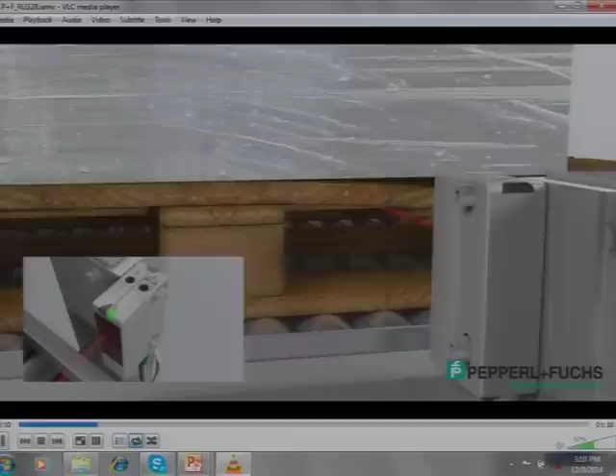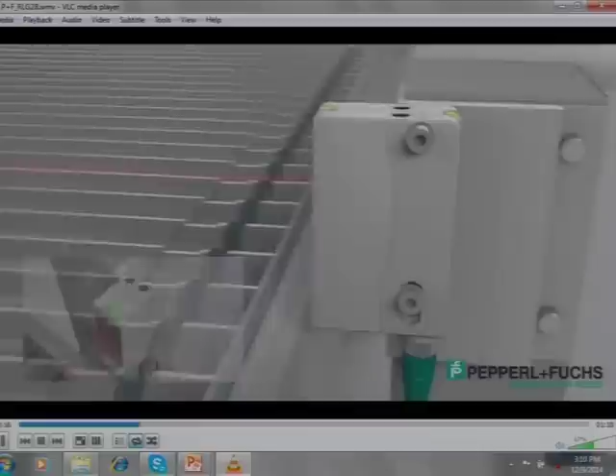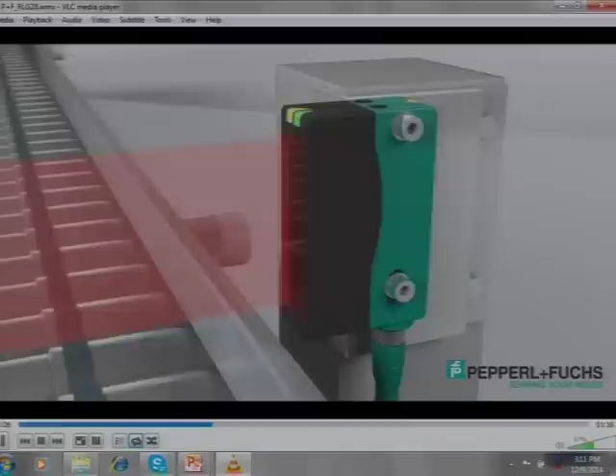So, this is again a conveyor. You have this sensor on one side and the reflector on the other side. As this pallet is going, it is supposed to sense this pallet. Now, these are different types of retroreflective sensors. There is a fine beam retroreflective sensor, that means only a fine beam is going and hitting the reflector and coming back. It does have a drawback, because if the components are not uniform, like what's happening here. So, for that there is a retroreflective sensor which has a band of beam.